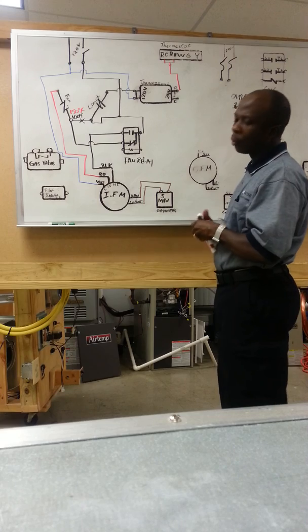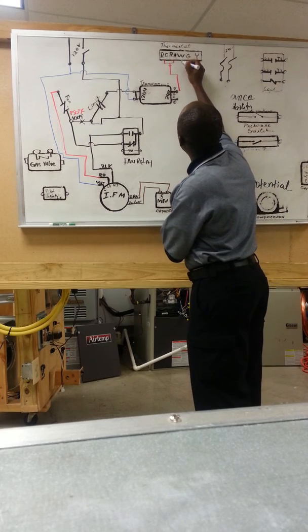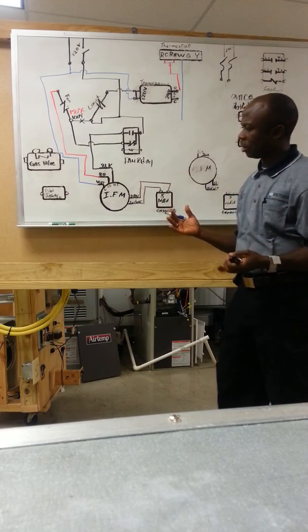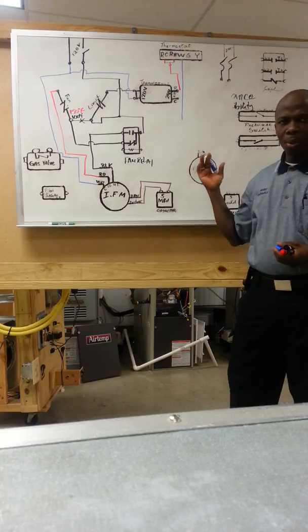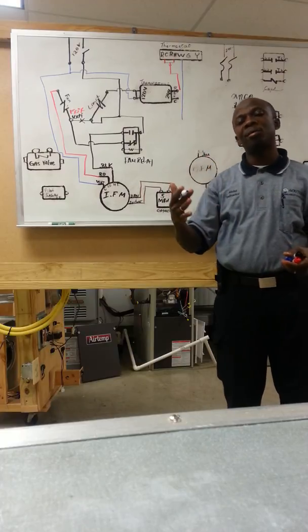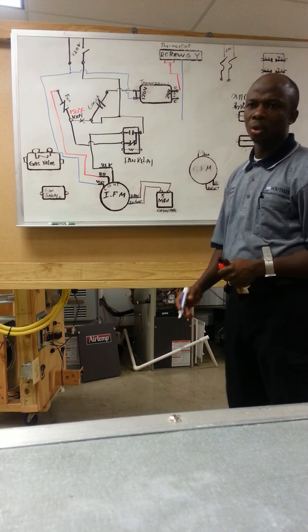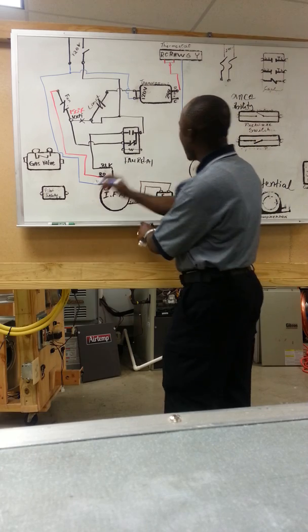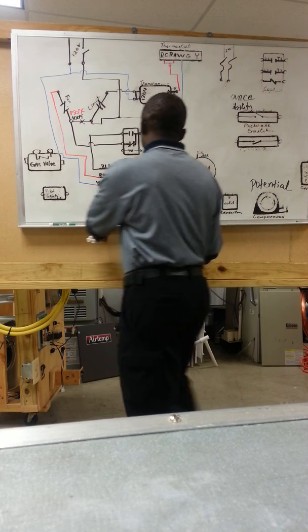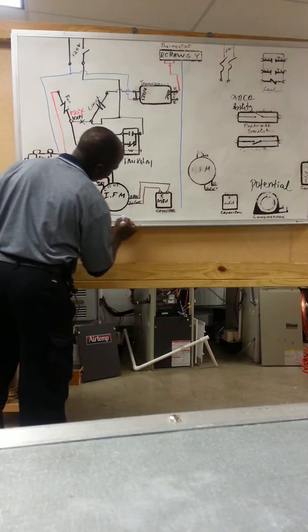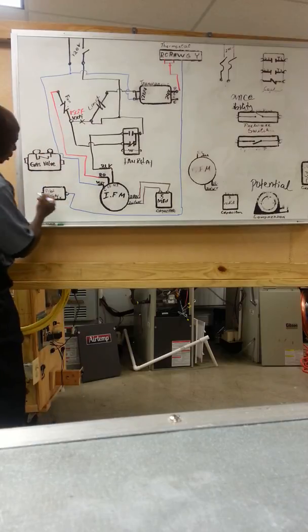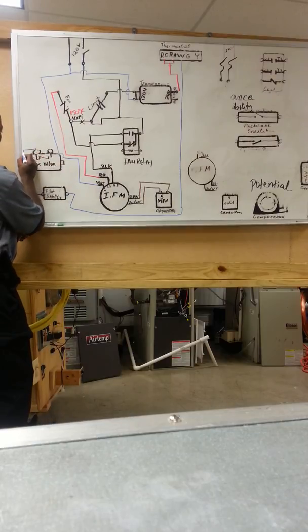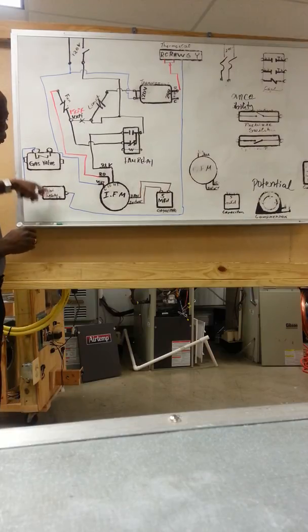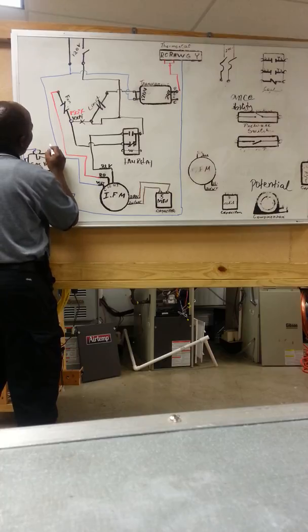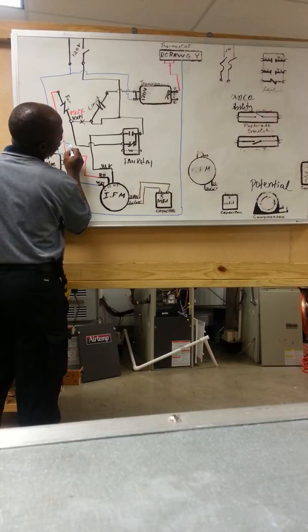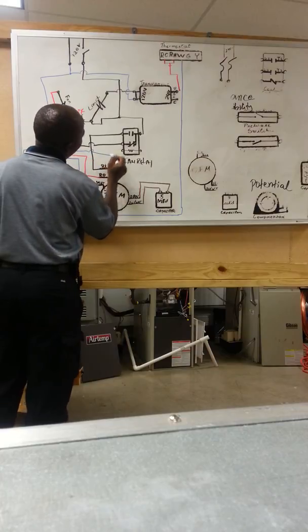So now what we have to do, we have to get the heating circuit, which is W, coming down. If you have any safeties in this feature here, when the power comes from W, which is a heating circuit from the thermostat, it has to go through all the safeties before it gets to the gas valve and goes back to the transformer to complete the circuit. So here we have a pilot safety, which is the only safety in this particular circuit here. So we're going to send power into the pilot safety. The pilot safety is having power coming in. The power is going to get out of the pilot safety into the gas valve. Now we have sent power to the gas valve. The power is going to get out from the gas valve. This power should be going to the transformer common.